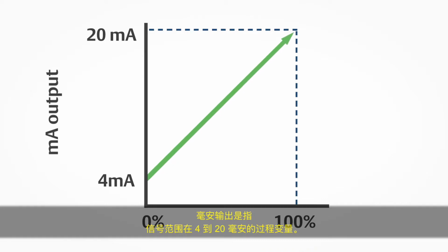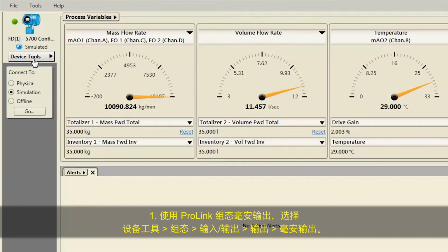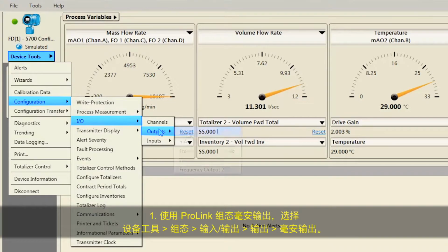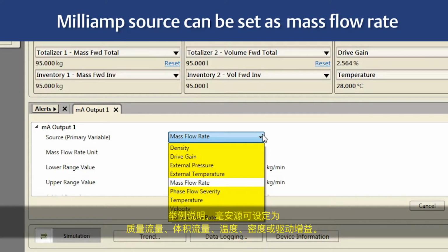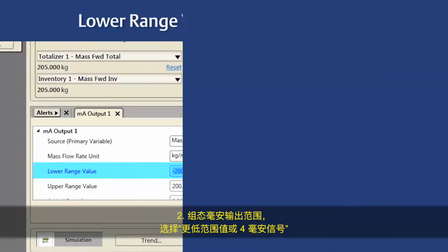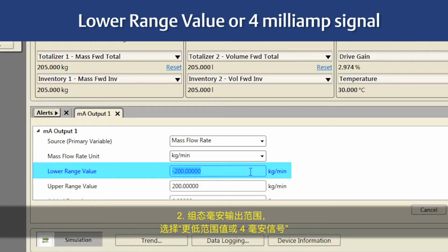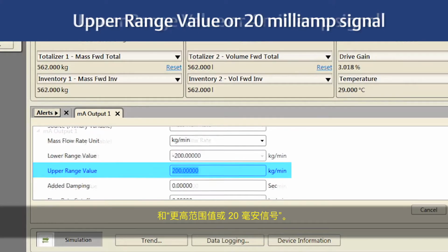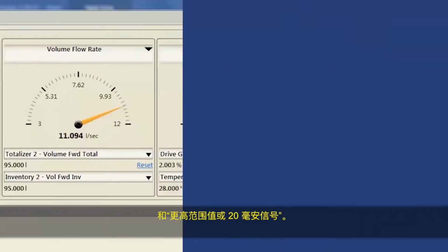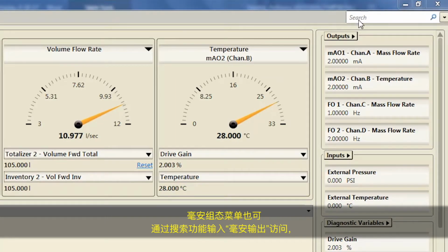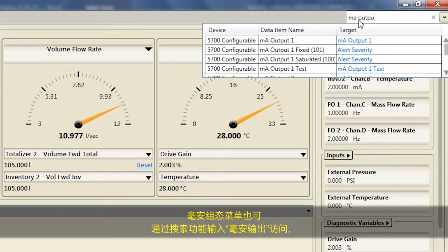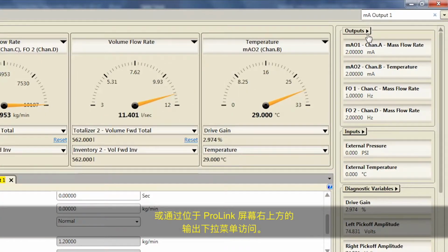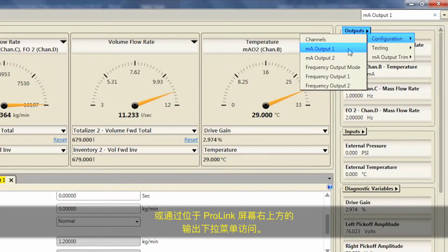The milliamp output represents a process variable in proportion to a signal range of 4 to 20 milliamps. First, configure the milliamp output. Using ProLink, select Device Tools, Configuration, I/O, Outputs, Milliamp Output 1. For example, the milliamp source can be set as mass flow rate, volume rate, temperature, density, or drive gain. Second, configure the range for the milliamp output by selecting lower range value or 4 milliamp signal and upper range value or 20 milliamp signal. The milliamp configuration menu can also be accessed by using the search function by typing in MA output or using the Outputs pull-down menu located at the top right of the ProLink screen.